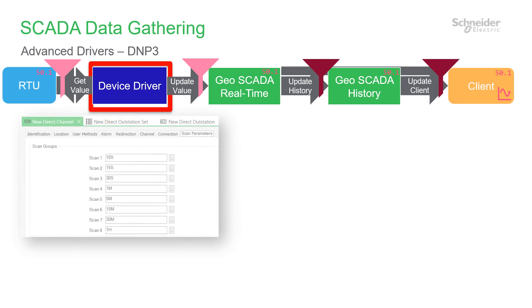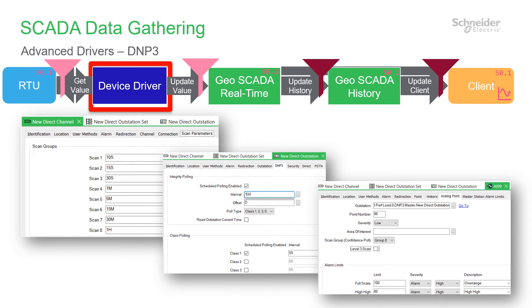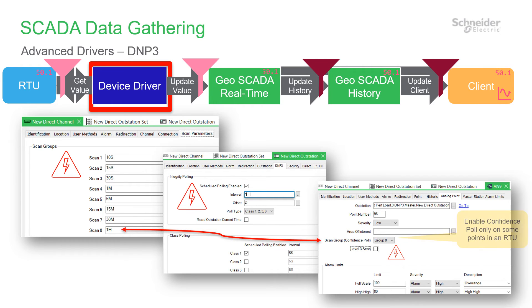For DNP3, the objective of the configuration is to filter the useful information from the data source using events. Events can be polled for by the driver, or sent unsolicited by the data source if the network permits. Events could be digital state changes, analogue limit crossings, report deadband, or periodic updates. They can be supplemented by slower periodic scanning using scan groups. Our advice is to pick a slow confidence poll and don't abuse this privilege, which will cascade to poor performance if unchecked. Even more concern is over the scheduled integrity poll, as this is the DNP3 terminology for whole device confidence polling and is often abused. Again, this is a complex area, and I recommend further reading of the documentation.